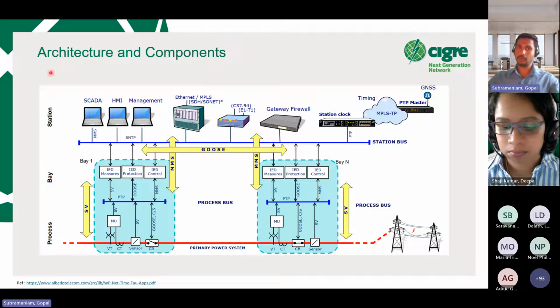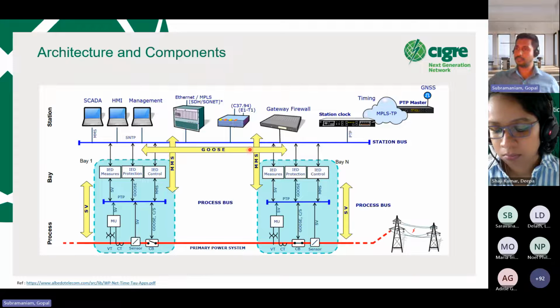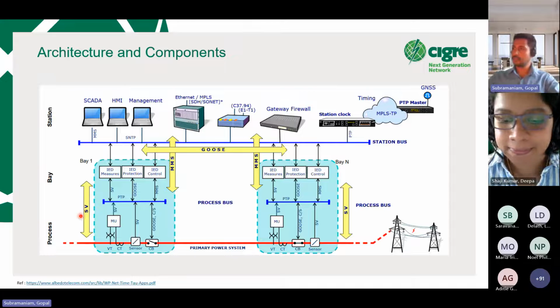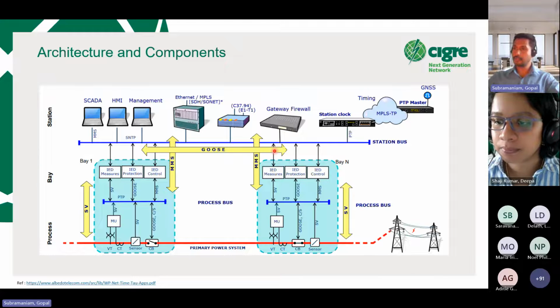So this is the overall architecture for the 61850 protocol, and we have different communication pathways or messaging systems within 61850. The most commonly used, you might see, are MMS, manufacturing message specification, then GOOSE, generic object oriented substation event, and sample values. GOOSE is a peer-to-peer communication, information sharing between IEDs to share switch statuses between different IEDs, and MMS is a communication between the bay level devices and the SCADA.